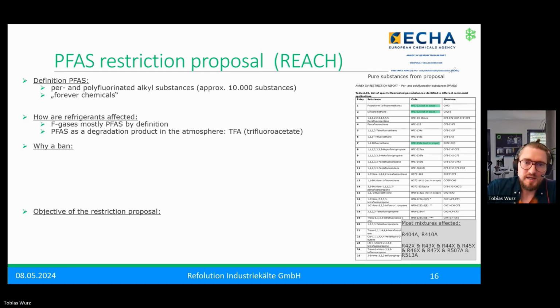Additionally, to mention here, the F-gases - most of these F-gases that should now be regulated by the PFAS proposal - when they go to the atmosphere, beside the R23 degradation I mentioned, we have this degradation to TFA, which is trifluoroacetate. And this means that we have PFAS in our drinking water generated by the atmospheric degradation of refrigerant, because no refrigerant system is perfectly leak tight.